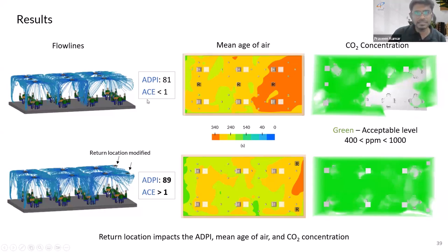The air change effectiveness is kind of worrying because it's less than one. Less than one indicates the old or exhaled air is recirculated in the space, which is evident from the mean age of air. The higher color indicates older air, showing how long it takes for the air to recirculate before it returns through the exhaust. This is also confirmed by the CO2 concentration cloud.